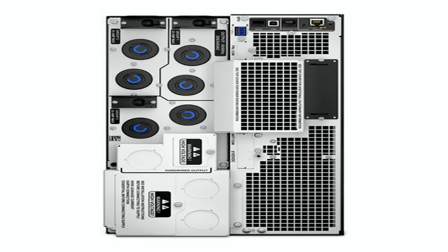The automatic internal bypass is another feature that only makes sense once you've lived through a power hiccup. Imagine you're performing a firmware upgrade on a core switch, and the UPS itself decides to reboot because of an internal fault. With a traditional UPS, your switch would lose power and you'd be left troubleshooting a network outage. The SRT8KXLT's internal bypass automatically reroutes the load around the UPS in the event of a UPS failure, keeping the power path open without a hiccup. In real life, that means you can finish your upgrade, walk away, and not have to answer a frantic Slack message about why the whole floor went dark.